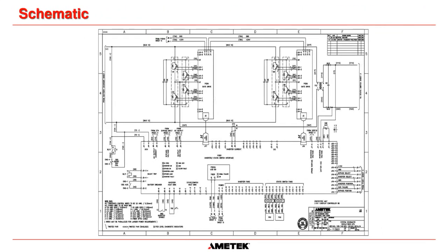And once again, to show you it in one of our AMETEK SAI drawings, this is the exact same H bridge. And in this circumstance, we have put two pairs of IGBTs in parallel, but we still would have Q1, Q3, Q2, and Q4. You can treat them as basically one IGBT each. Okay. My drawings are quite poor, but just because we put them in parallel, and in truth, we can put up to about 6, maybe even 8, I can't remember what the maximum number of IGBTs that we put in parallel is, to get higher capacity ratings out of our UPSs.